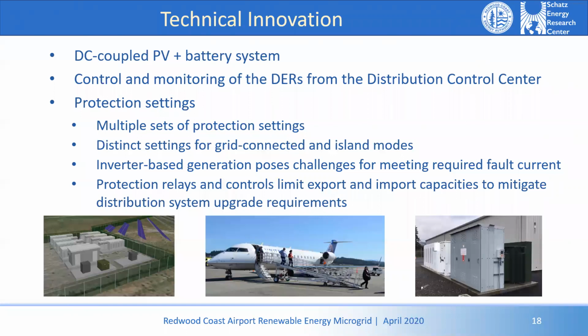And then finally, it's a 100% renewable microgrid. It's solar and battery powered only. Interconnecting inverter-based distributed generators on the grid creates some issues, certainly in island mode, with regard to protection settings and achieving adequate fault current. If there's a fault, you need to make sure that you can trip your breakers and have coordinated fault modes. So we're actually going to be using two different settings for the fault currents. One will be for grid connected mode, the other for island mode, and the controllers will keep track of that and manage that.